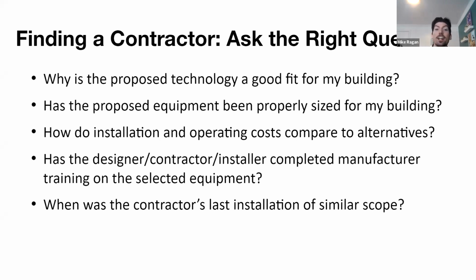All right, has the designer, contractor, or installer completed the manufacturer training on the selected equipment? Please feel free to ask this question to the person who's going to be installing your equipment. We want to make sure that they know how to install our equipment. I'm a Mitsubishi representative. If I find out that a contractor installing the equipment has only gone through Daikin training, that's a concern. There are different considerations and different install practices for different manufacturers. Different manufacturers have different rules you need to follow about pipe bends or traps in the lines, or oil considerations. We want to make sure they've gone through the manufacturer-specific training.